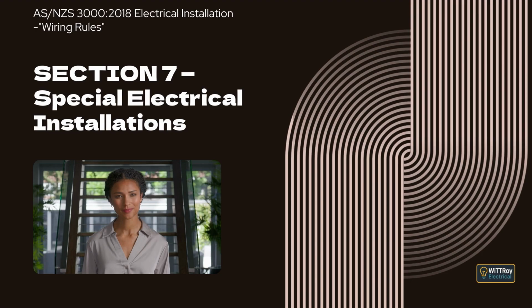Clause 7.2.7.2.1 Types of wiring system for air handling systems. This clause explains that wiring systems supplying air handling systems must comply with AS/NZS 3013 and use the wiring system classification specified by the relevant installation standard. Where no wiring system classification is specified, the wiring must be capable of maintaining supply when exposed to fire or mechanical damage, or must maintain supply when exposed to fire while being protected against mechanical damage, either through an effective enclosure or by location. It also explains that these protection requirements do not apply where the wiring is already installed in an enclosure or location that provides adequate fire and mechanical protection.